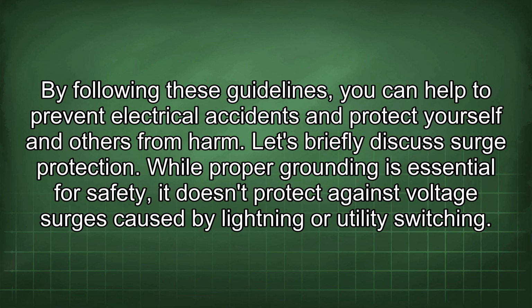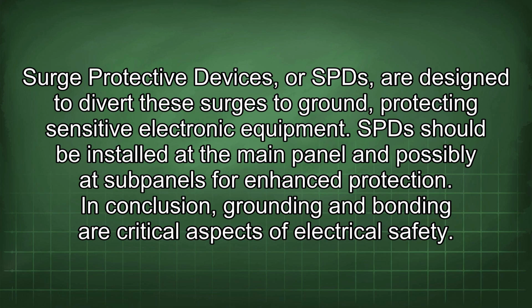Let's briefly discuss surge protection. While proper grounding is essential for safety, it doesn't protect against voltage surges caused by lightning or utility switching. Surge protective devices, or SPDs, are designed to divert these surges to ground, protecting sensitive electronic equipment. SPDs should be installed at the main panel and possibly at subpanels for enhanced protection.